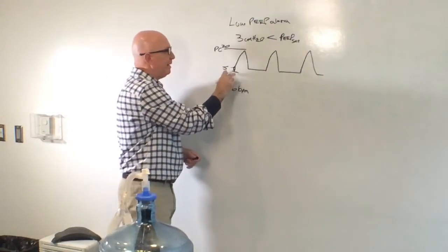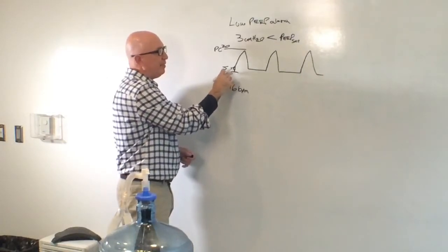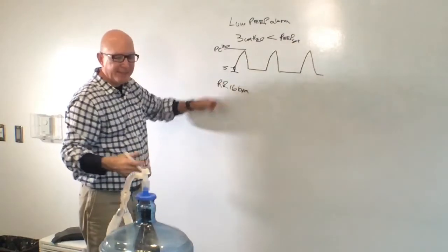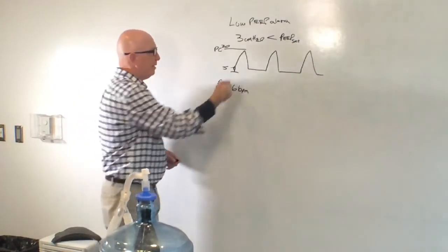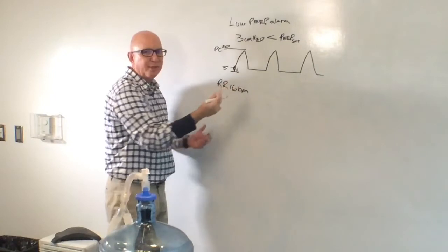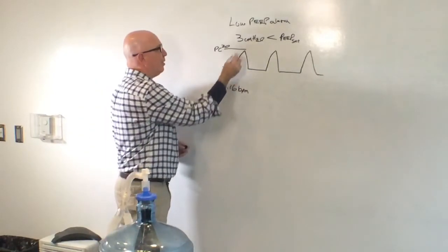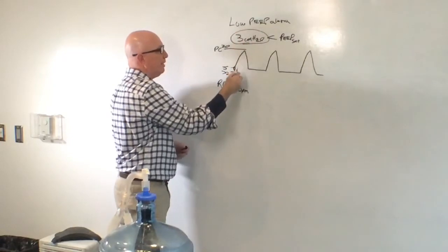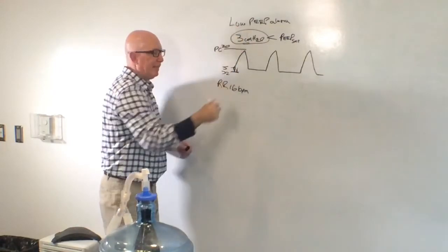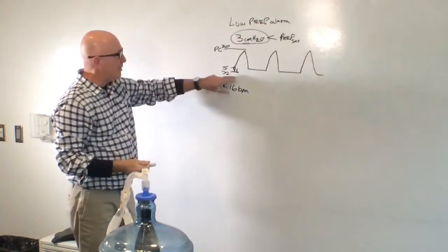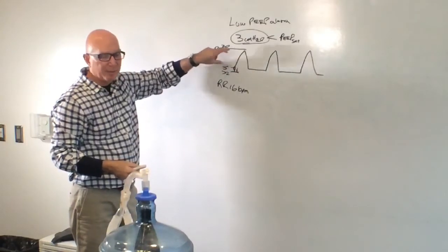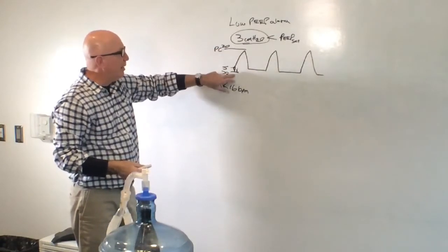So in other words, if the patient's inspiratory effort exceeds the flow that's in the ventilator circuit, the pressure is going to drop. It has no choice. It has to drop. And if it drops to less than 2 centimeters of water, which exceeds this threshold, you will get a low PEEP alarm.